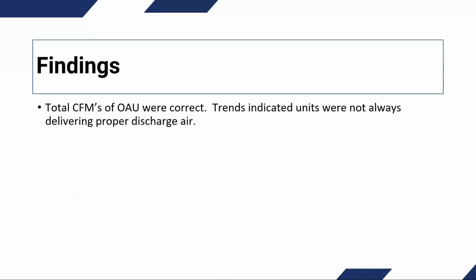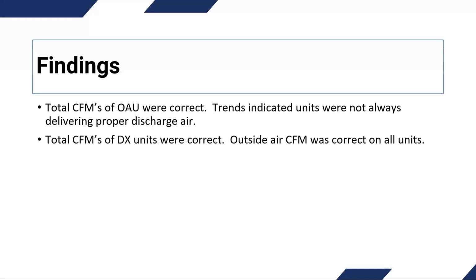What we found on this particular project were, fortunately, CFMs on the outside air units right where we had them on the test and balance report. So that was a positive. But the trends indicated that the units were not always operating properly. The discharge air was not always where it needed to be. On the DX units, fortunately, again, the CFMs were correct. The outside air was correct. So as far as the proportion was concerned, everything was within design parameters.